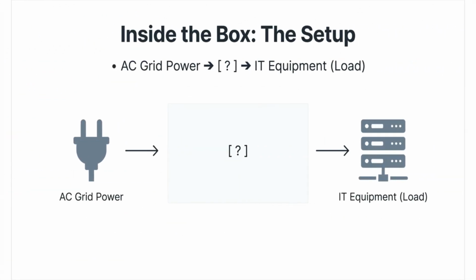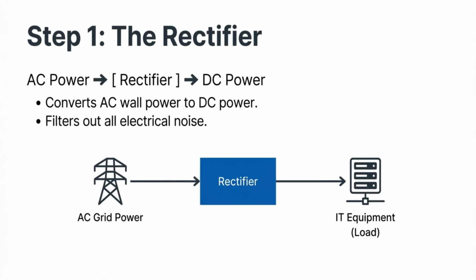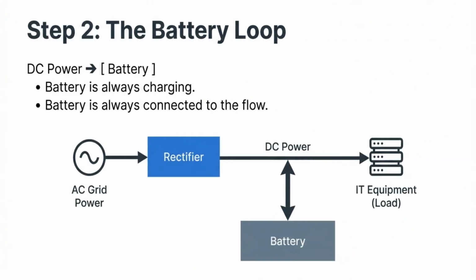Let's look inside the box at the double conversion setup. Power flows from the AC grid, through the UPS, and then to your IT equipment. Step 1 involves the rectifier, which converts AC wall power to DC power and filters out all electrical noise, delivering clean DC power. Step 2 is the battery loop.